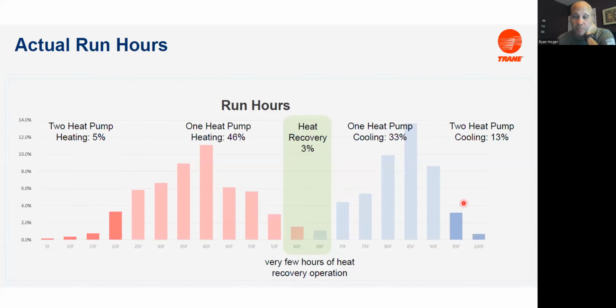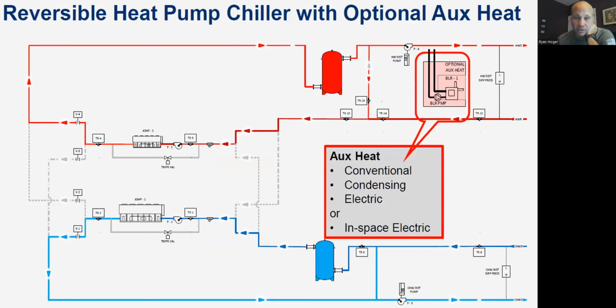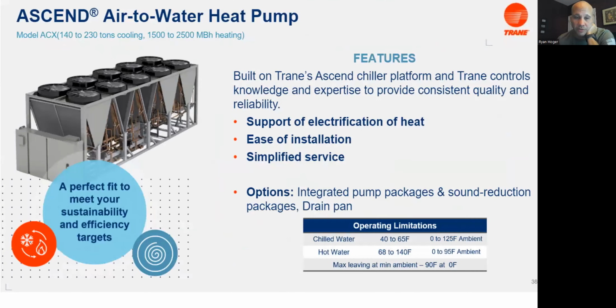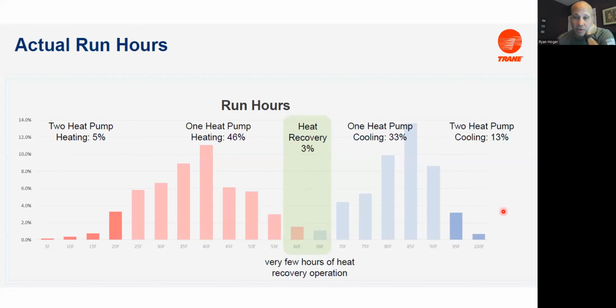In terms of operation hours, obviously this chart would be different depending on your project. But what we're showing here is percentage of run hours over the course of a year, 8,760 hours a year, whatever it is. So this is this machine in this example here, where I have two machines, one set up for heating, one set up for cooling, but they could help each other out. So that's this scenario here. So how often do I need both heat pump chillers running cooling? It's, you know, whatever this is, 3% plus 1%, 4% of the year, or actually, no, sorry. Two heat pumps cooling, 13%, but those don't add up to 13% visually. Oh, because there's in between 96, 97, 98, 99.